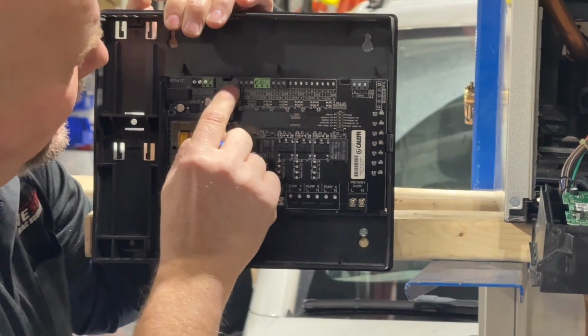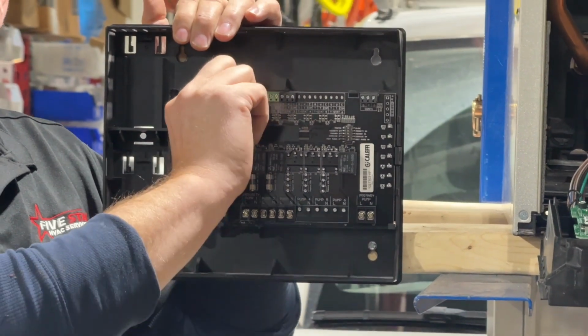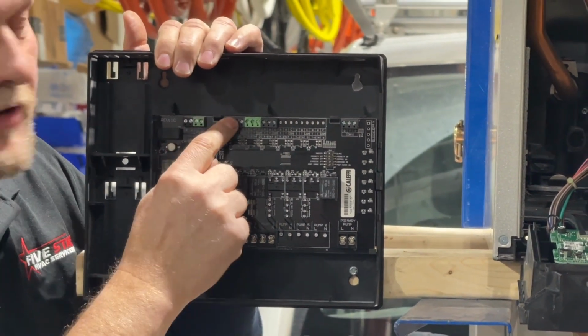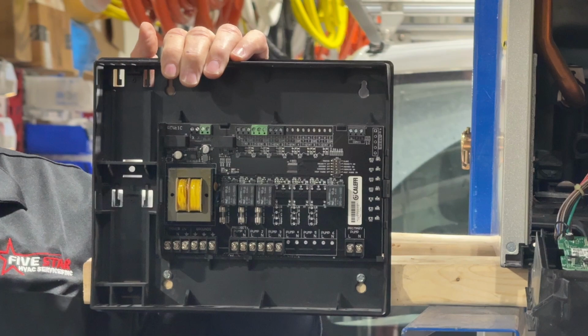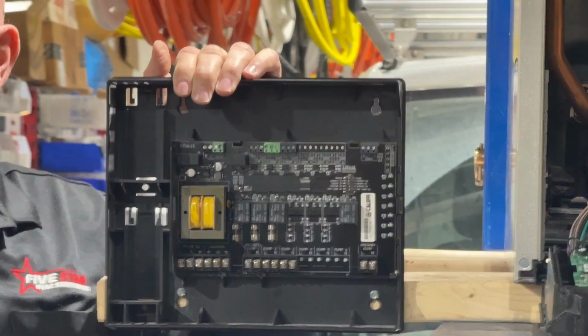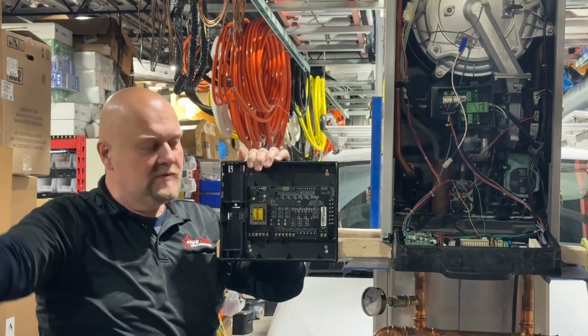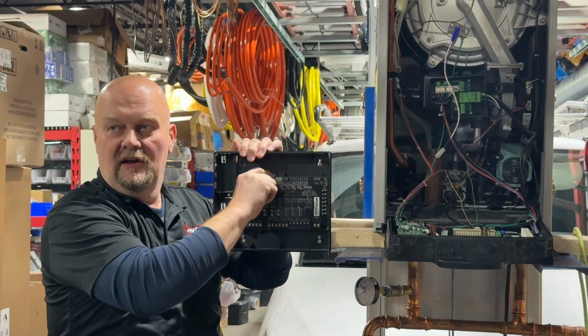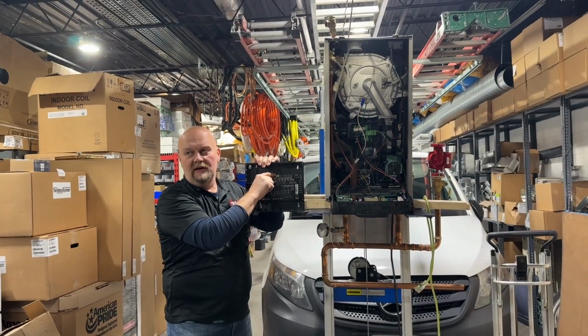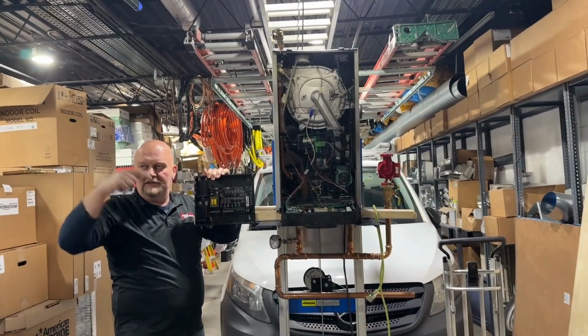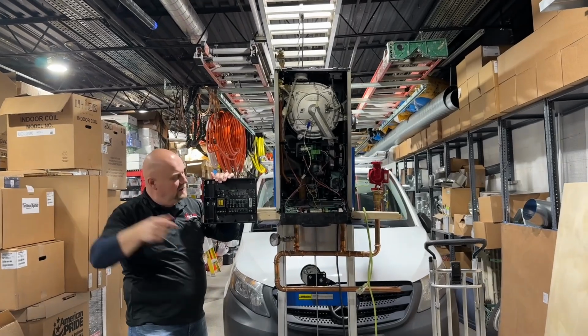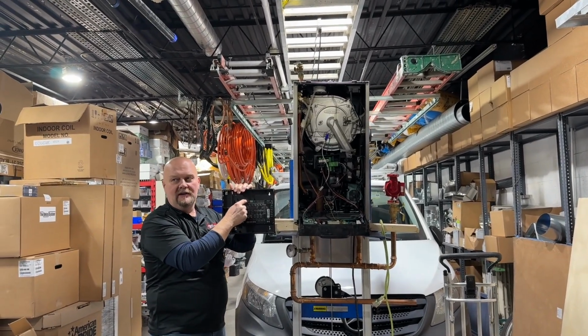So you're gonna see R, W, and C for each thermostat. So from here, you're gonna go to an individual thermostat in someone's house. Let's say a basement zone. Basement zone is gonna connect to these 3 wires, or 2 of them, R and W. Whenever the thermostat calls for heat, it'll close between R and W.